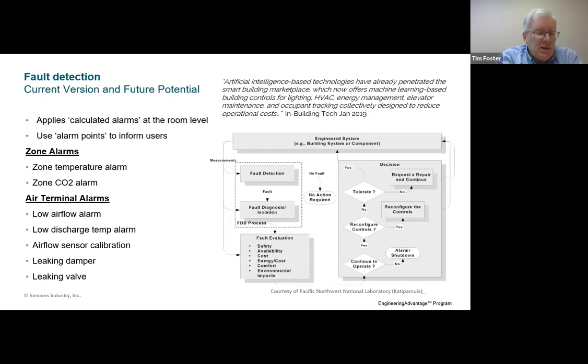Typically we see, through fault detection, and another term for it is continuous commissioning, through this automated fault detection or continuous commissioning approach, typically you see 10 to 20% energy savings, kind of a rule of thumb, sometimes more, depending on where you're at. But really the opportunity for manpower or energy or operational efficiency savings is probably greater than that. I mean, we might see like a 2-to-1 between energy and operational efficiency.